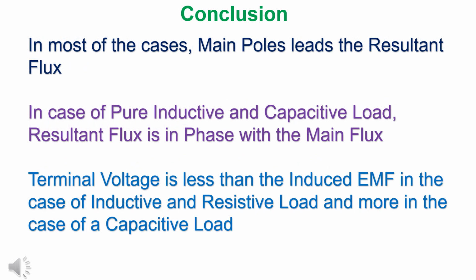In most of the cases, main flux is ahead of resultant flux. In case of pure inductive and capacitive load, these fluxes are in phase. Terminal voltage is less than induced EMF in the case of inductive load and more in the case of a capacitive load.